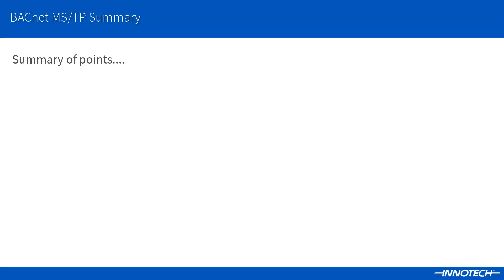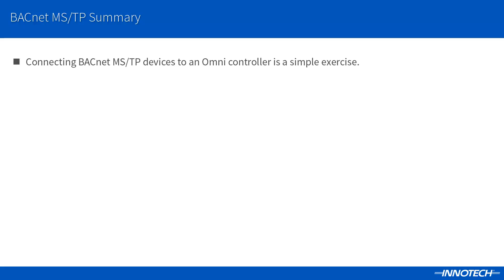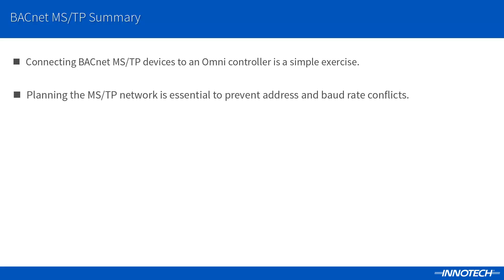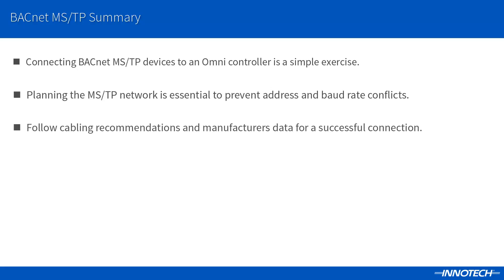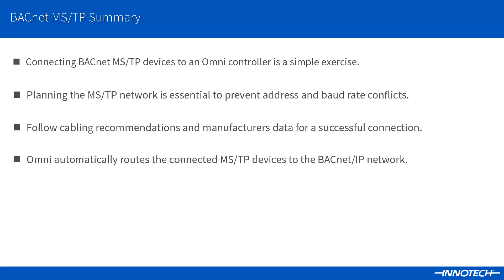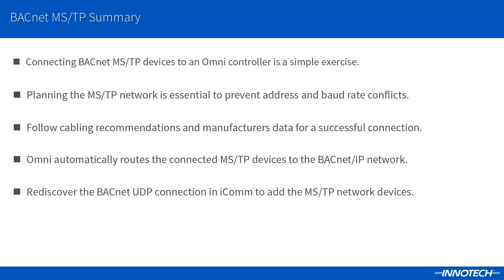To summarize what we have seen, connecting BACnet MSTP devices to an Omni controller is a fairly simple exercise when all the procedures outlined in this presentation are followed. Planning the MSTP network connection is essential to ensure that there are no BACnet instance, MSTP address, and baud rate conflicts. Following the cabling recommendations and manufacturer's data is important for a successful connection. When the Omni comms port is configured for BACnet MSTP communications, Omni automatically routes the connected MSTP device data to the BACnet IP network. After the network connection is complete, rediscover the BACnet UDP connection in iComm to add the new MSTP network devices. The BACnet data points can then be used as required in your project for data sharing or within other Innotech software packages such as Magellan or Chronicle.